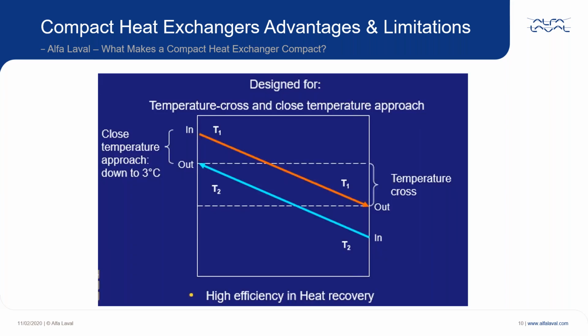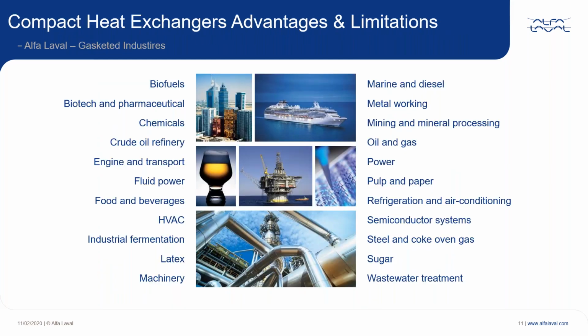Because we use counter-current flows in our exchangers, we can get very close temperature approaches. It says here down to 3 degrees. You can go closer, but the size of the heat exchanger will exponentially get bigger. So gasketed heat exchangers are used in many industries. The main ones I deal with, I won't go through them all, but it's oil and gas, power, HVAC, pulp and paper, and metalworking, just as a few.